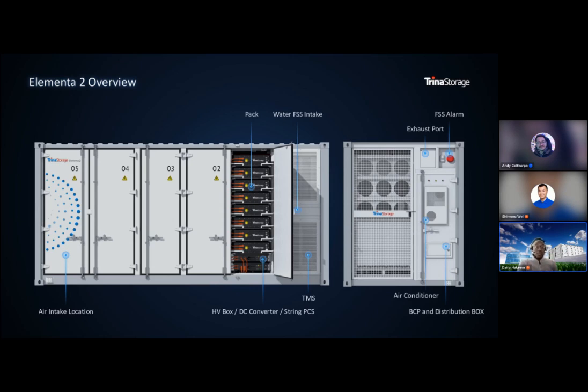Looking at the overall picture, we have exhaust and intake vents on the Elementa, and a pressure valve on the modules themselves. On the module, or pack as labeled on screen, we have a pressure valve that's a means for the module to breathe. I say breathe because before an event occurs, it will most likely release some gases. We want to let the module breathe and eject any flammable gases or gases that aren't supposed to be in there through the exhaust or intake valve. Finally, there are specific components that make up the overall fire suppression system.